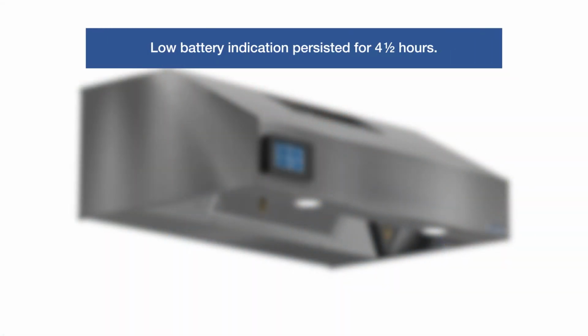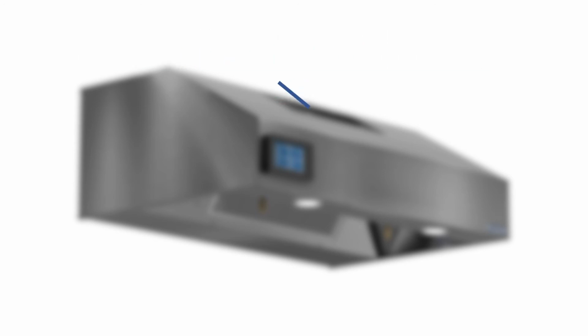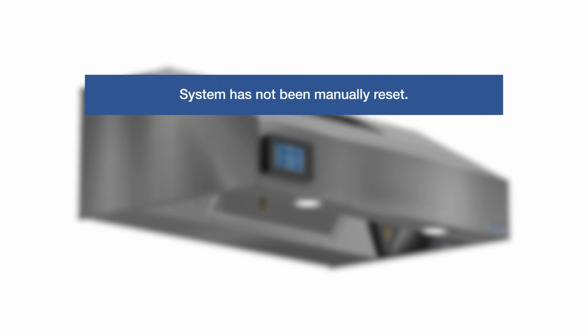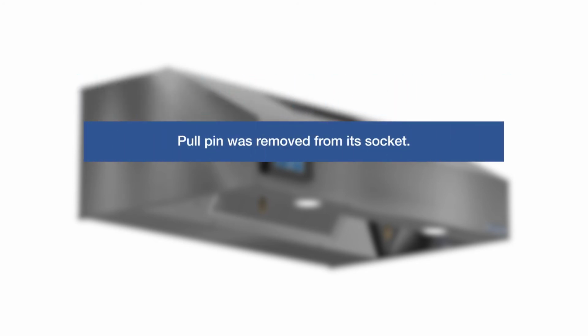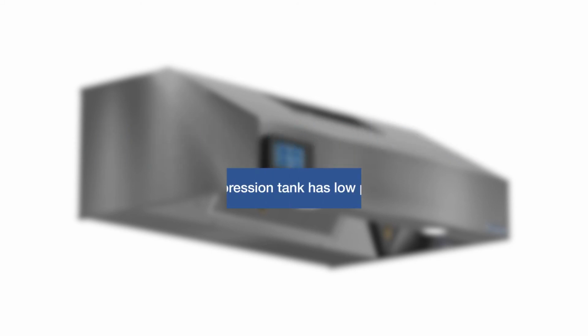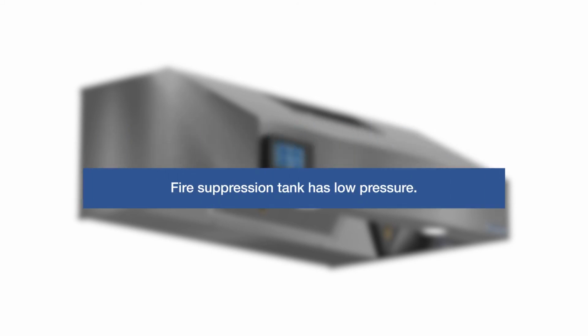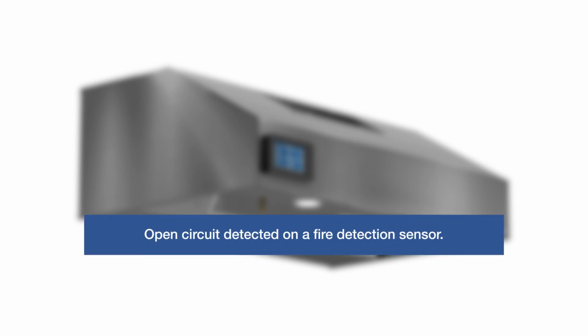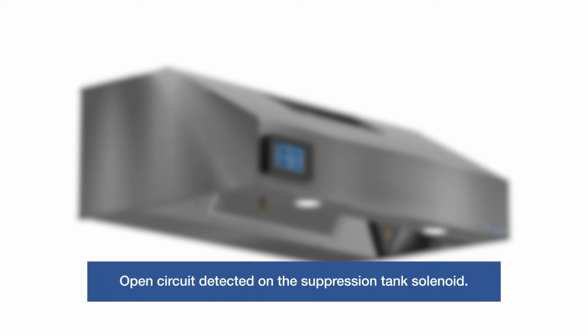1. Low battery indication has persisted for at least 4.5 hours. 2. A test sequence was executed successfully and the system has not been manually reset. 3. The pull pin was removed from its socket. 4. The fire suppression tank has low pressure. 5. An open circuit was detected on one of the fire detection sensors. 6. An open circuit was detected on the suppression tank solenoid.